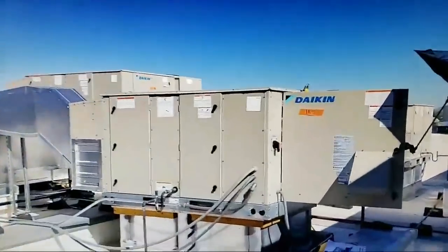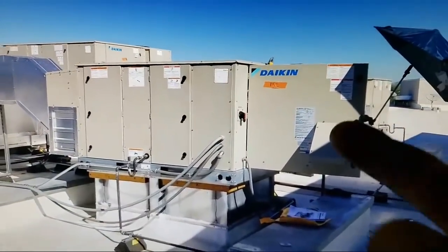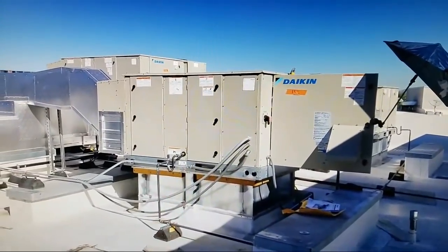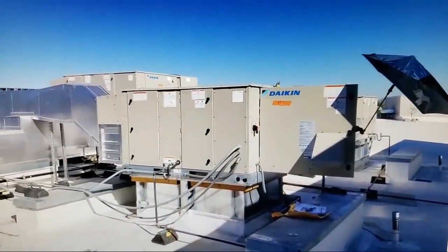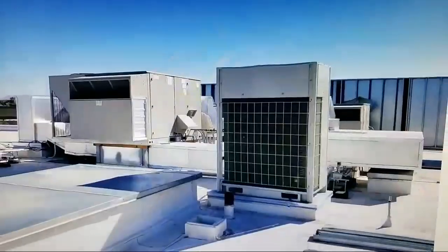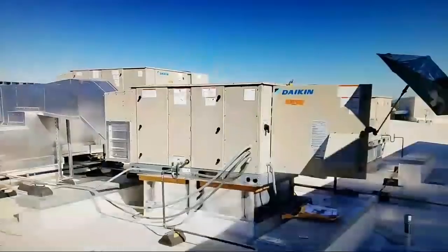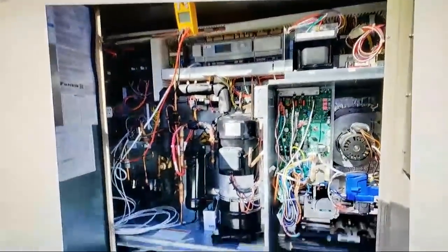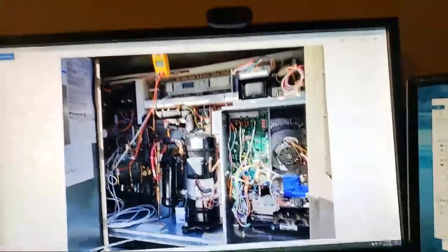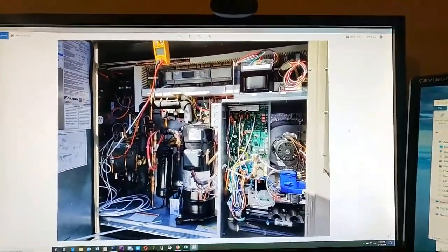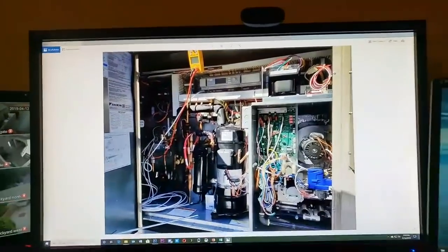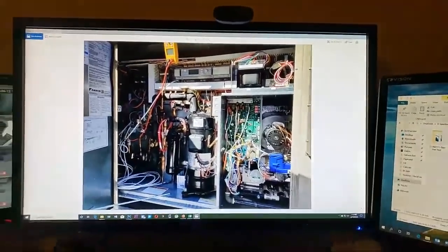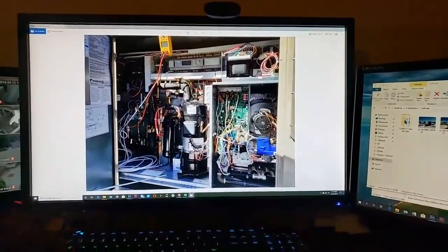It's probably the Goodman lover that chimed in earlier. Told me the gauges were on the wrong port. But no, that's the suction. That dome right there, that's suction pressure. It's hot gas down bottom because this is a rotary vane compressor. That's your discharge coming out right here. Does this loop-de-loop. Comes up. There's my port I had my gauge on. On the other one. It goes around. It goes down into the oil separator. And the oil, then the discharge continues out. Goes over and drops into the reversing valve. If it has one, this was a gas reheat. This picture is taken in 2017. Yeah. So almost two years ago, I was there on that unit. All right. My video is going on forever, guys. It's Friday. You guys have a good weekend.